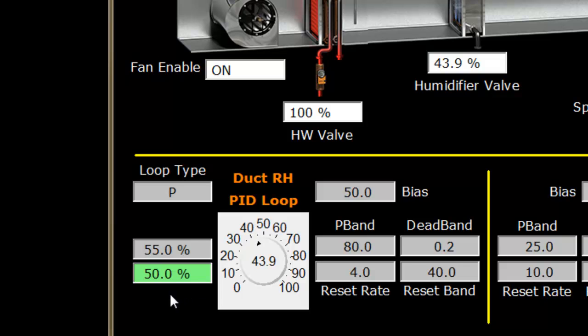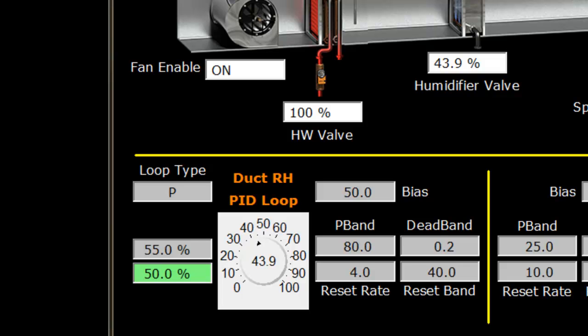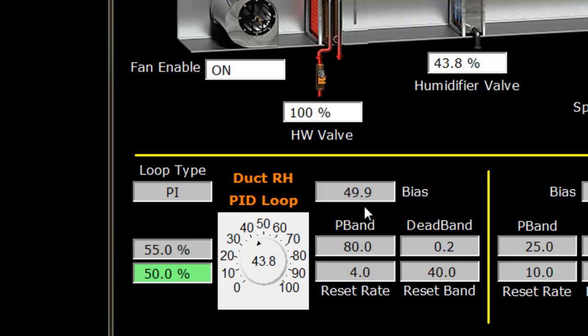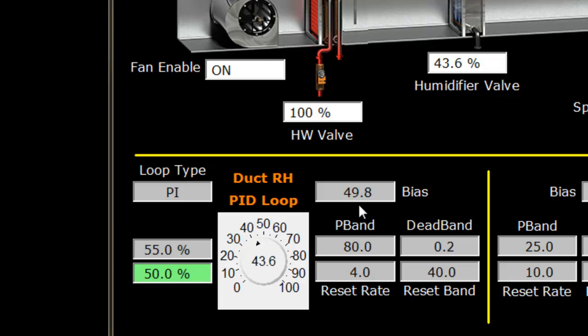The way we do that is by adding the integral proportion. I'm going to make that change here, and you'll notice the loop type will change to a PI loop. When that happens, we'll watch our bias take down—it went from 50 to 49.9 and slowly but surely will continue to update.